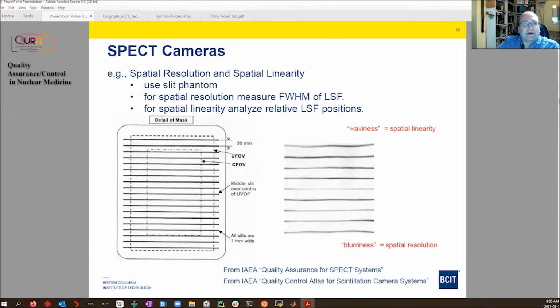Linearity is tested by a phantom where you have lead strips with 1 millimeter gaps between them, arranged so that the center of the gaps is 30 millimeters. You put this on the detector and you set up a flood field. The only gamma rays that actually hit the detector are the ones on these lines. And this is what you don't want to see. If the linearity correction has been calibrated, you still see this, something's wrong. It's probably that you made a mistake in the linearity calibration. So this waviness is what we mean by linearity. How wide these lines are is what we mean by spatial resolution.